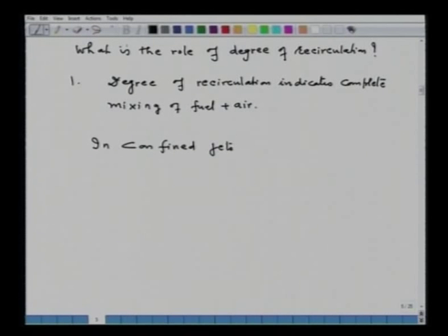In a confined jet, absence of recirculation causes a tendency for the flame to expand until it impinges on the furnace walls or load. If there is no recirculation or no pulling of exhaust gases, the flame spreads and may hit the refractory walls, destroying the refractory lining. A high-momentum recirculating jet will produce a stable, controllable flame. The proportion of primary air must be controlled so the momentum flow rate entrains both the surrounding and the exhaust gases.